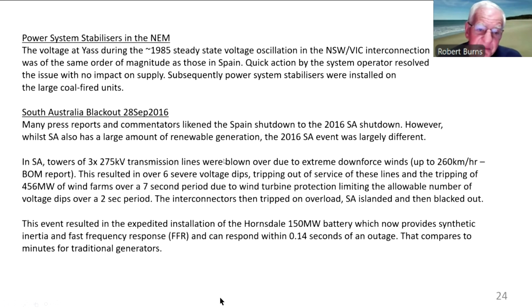So as I say, similarities, a lot of renewable energy there compared to Spain, but this was a major fault, a series of high voltage faults, where Spain was nothing. There was no actual fault on the system. It was just sitting there and started to get a wobble.